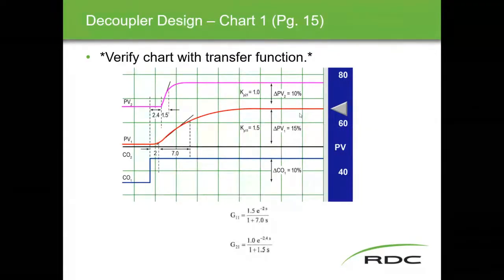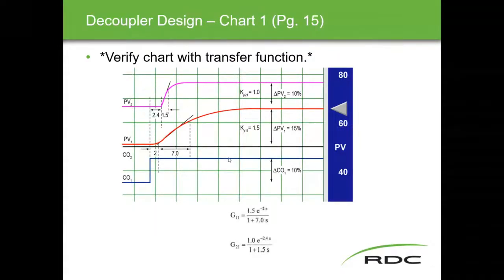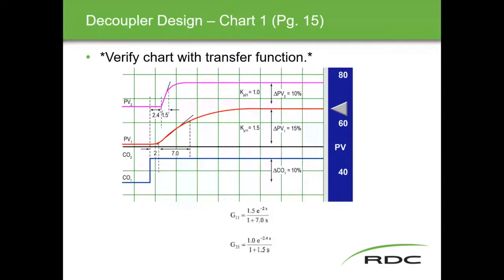We start with charts like we did last year to get the transfer functions. A controller output change of 10% gives us a gain of one. A 10% change producing a 15% response gives a gain of 1.5. Draw your intersecting line, your 63.2% dot, and get all your values to fill in the transfer function.